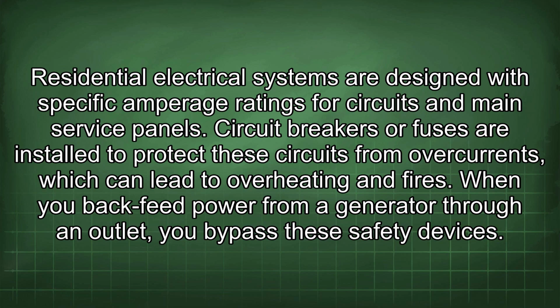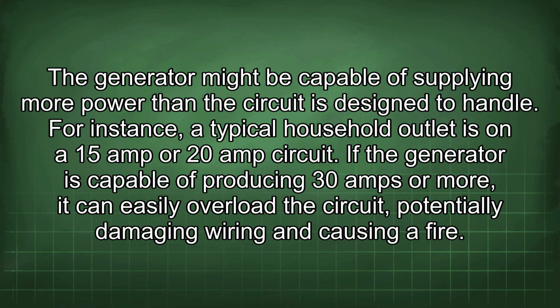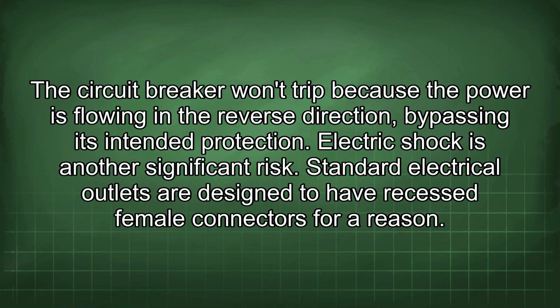Circuit breakers or fuses are installed to protect these circuits from overcurrents, which can lead to overheating and fires. When you backfeed power from a generator through an outlet, you bypass these safety devices. The generator might be capable of supplying more power than the circuit is designed to handle. For instance, a typical household outlet is on a 15 amp or 20 amp circuit. If the generator is capable of producing 30 amps or more, it can easily overload the circuit, potentially damaging wiring and causing a fire. The circuit breaker won't trip because the power is flowing in the reverse direction, bypassing its intended protection.